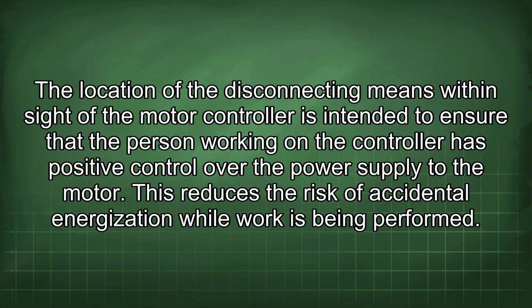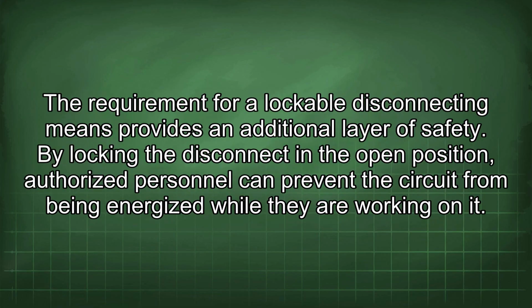The location of the disconnecting means within sight of the motor controller is intended to ensure that the person working on the controller has positive control over the power supply to the motor. This reduces the risk of accidental energization while work is being performed. The requirement for a lockable disconnecting means provides an additional layer of safety. By locking the disconnect in the open position, authorized personnel can prevent the circuit from being energized while they are working on it.